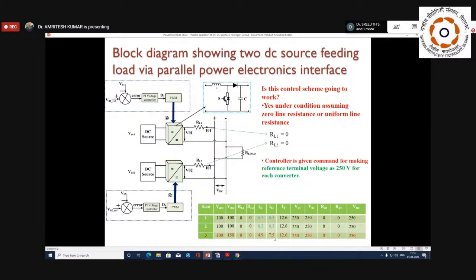So it means that if we are applying this control, then this control will work when we assume line resistance is 0, and it will have uniform sharing of power only if they have voltage sources of equal value. But suppose one source is higher, then the power transfer from the higher voltage source is going to be more, or it is going to control the DC grid. So suppose if we further increase the voltage of VDC2 to a higher voltage, then the DC microgrid voltage will be fully controlled by that DC source.